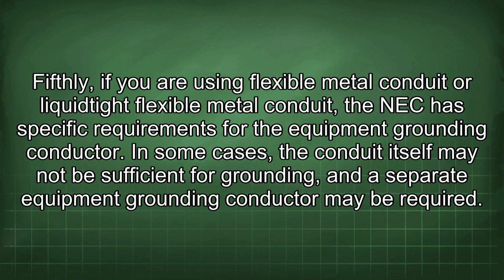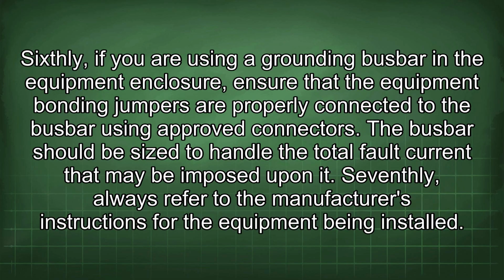Fifthly, if you are using flexible metal conduit or liquid-tight flexible metal conduit, the NEC has specific requirements for the equipment grounding conductor. In some cases, the conduit itself may not be sufficient for grounding, and a separate equipment grounding conductor may be required.